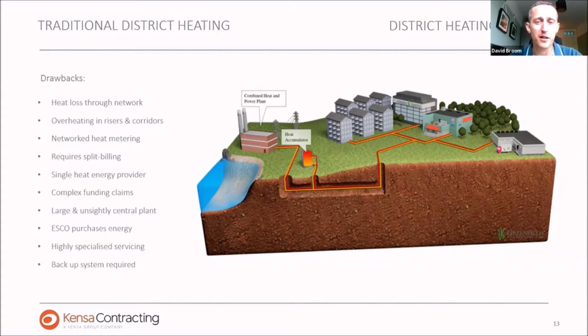If you put a heat pump in the middle of that picture, it gets even more difficult because, as I said, what we like to do is run it at as low a flow temperature as possible to maintain the efficiency of the heat pump. By running a high temperature network, we have to run the heat pump harder to deliver domestic hot water as well as space heating around the circuit, because the hot water system needs to be at a slightly higher temperature. So for all of those reasons and a bunch of others, we decided that we need to find a better way of attacking district heating using ground source heat pumps. And that's where the concept of shared ground loops came from, which is a concept we've pioneered for the last 7 or 8 years. Next slide, please.